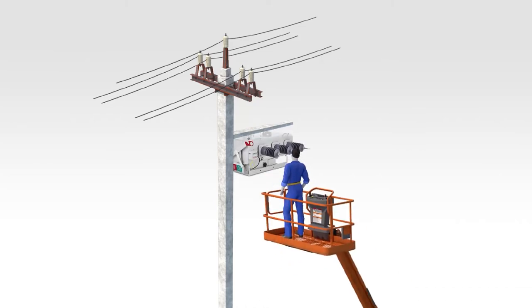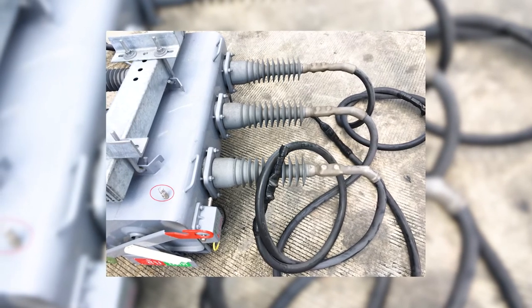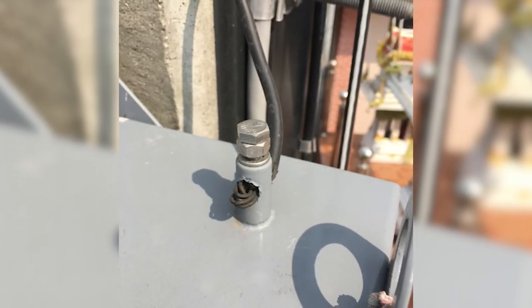Step 4: Use an electric repair hotline car to install the Rapier GX Load Break Switch on the electrical pole, carried out by experienced engineers. Step 5: Connect the HV ground to the HV ground rod. Step 6: Connect the LV ground to the LV ground rod.